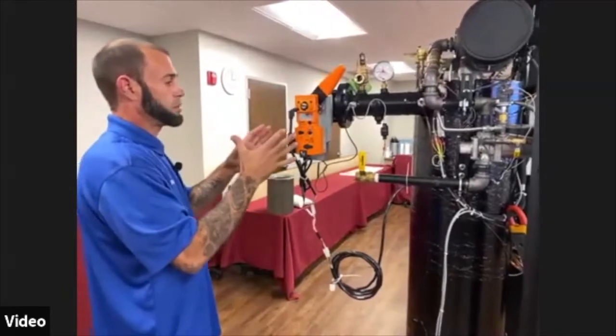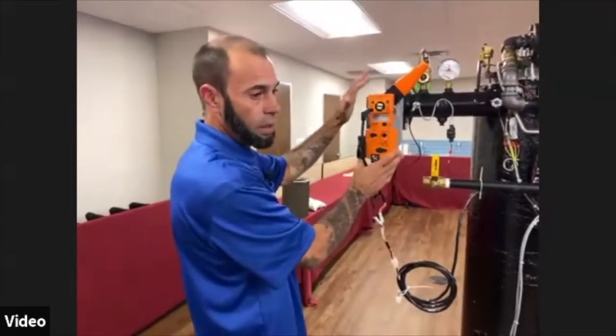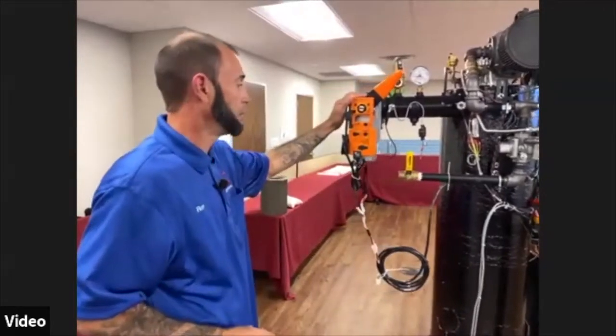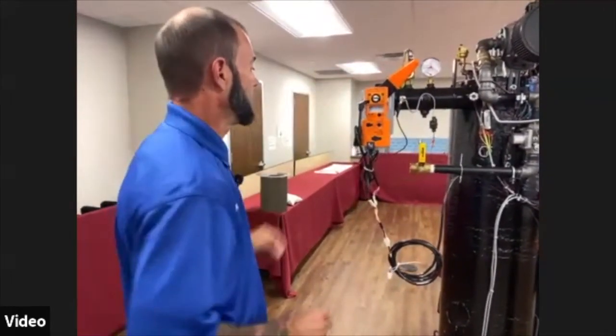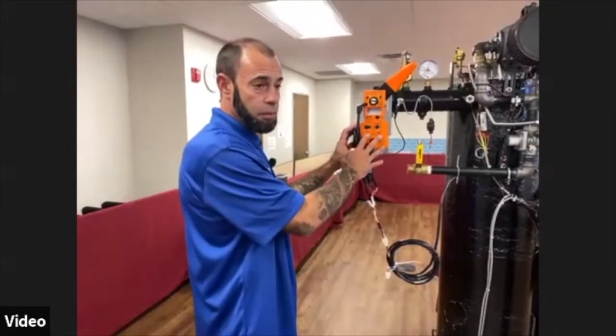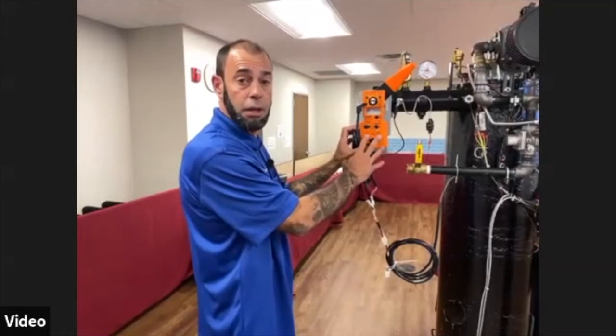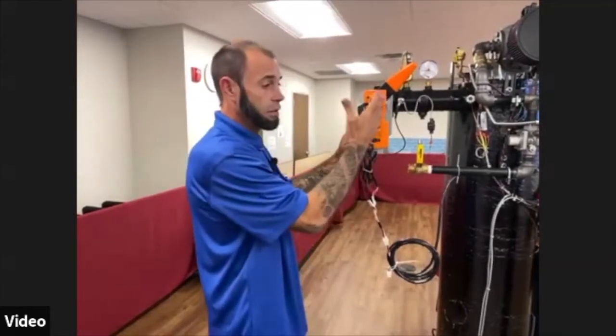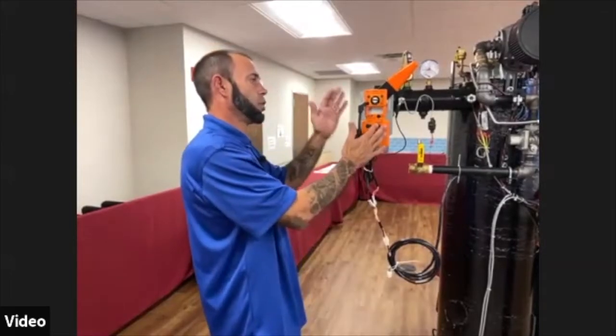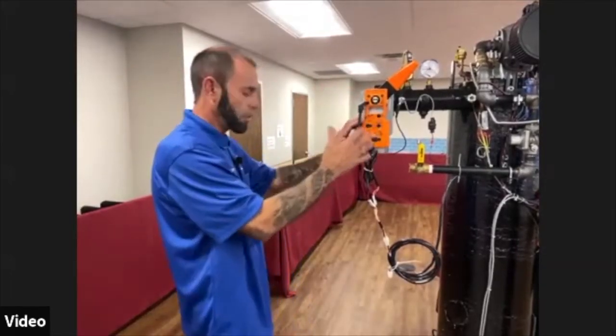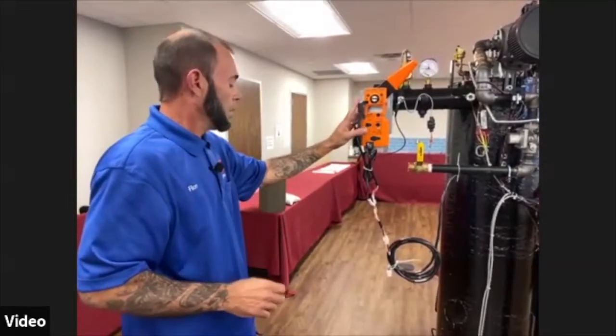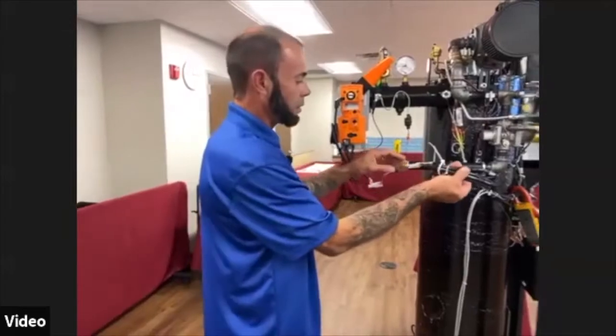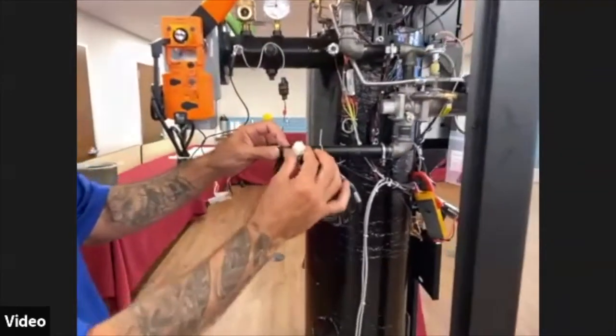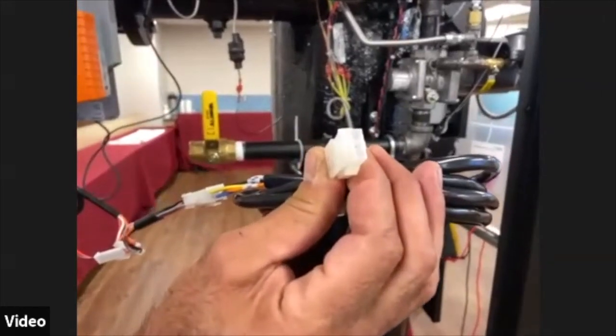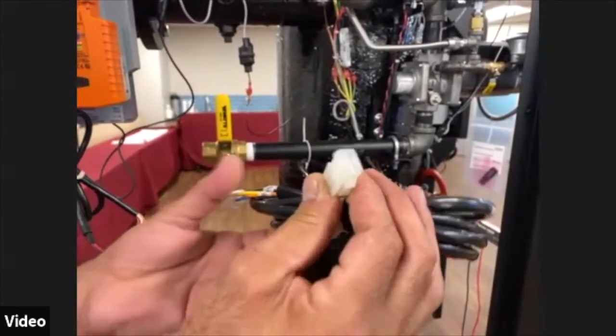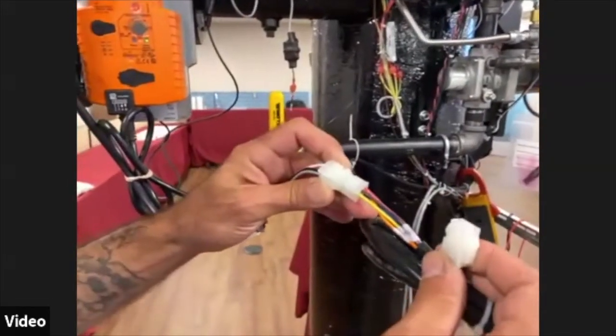This happens to be set up in a situation where we would be looking at doing a BST, and we have a boiler isolation valve supplied by the manufacturer with a built-in end switch. This would be something we'd like to use for BST when we're doing a variable primary. If we're doing variable primary, obviously the reason behind that is we want to make sure we have flow through boilers that are on and no flow through boilers that are off. So we're not mixing that. The manufacturer sends the wiring harness with this little jumper in it. So in the event that you might be doing a primary secondary and not using the actuators, you would just leave this jumper in, and that would make your connection for your end switch.